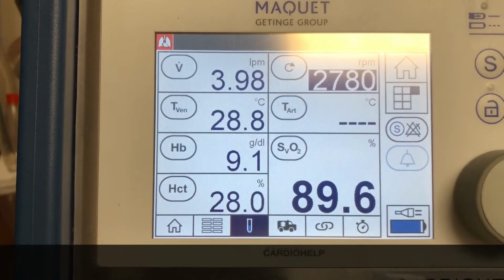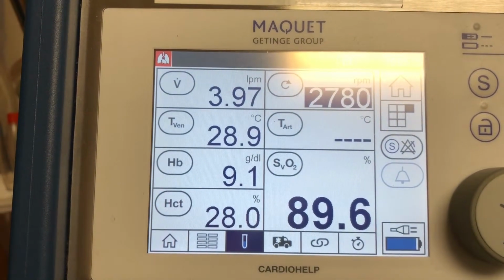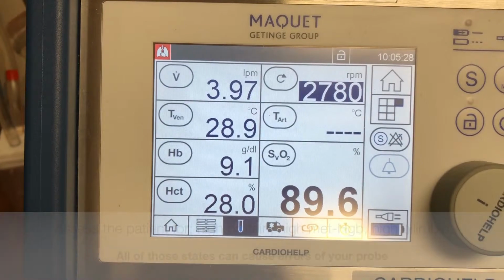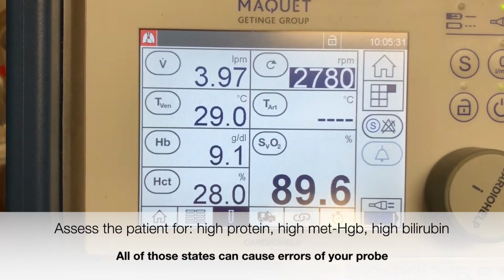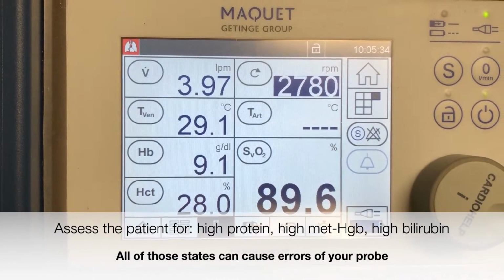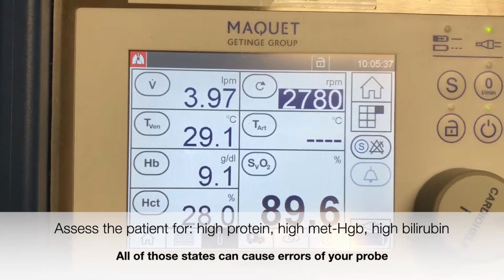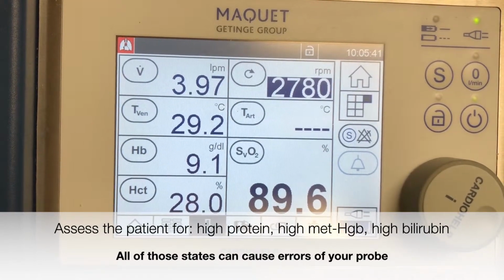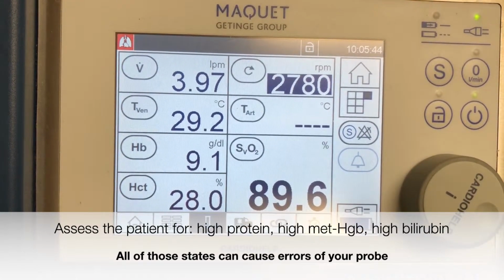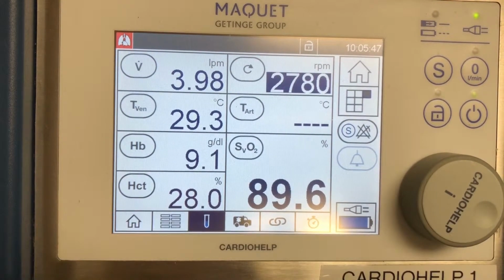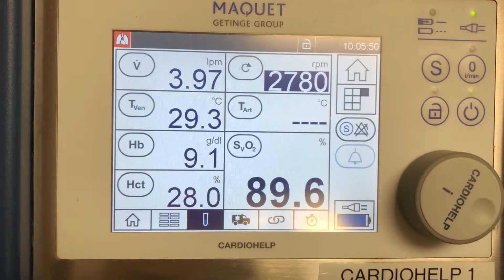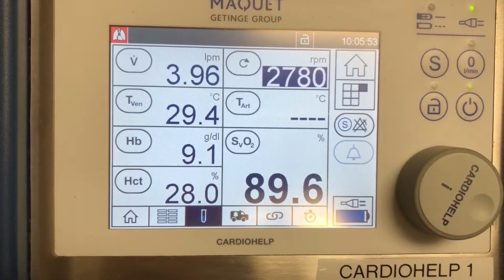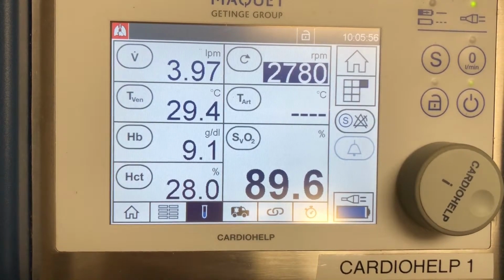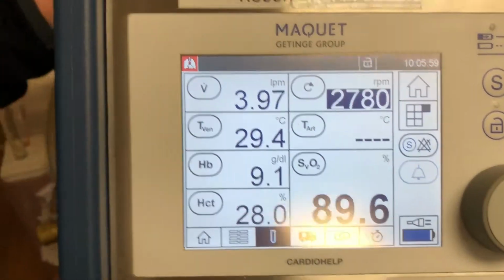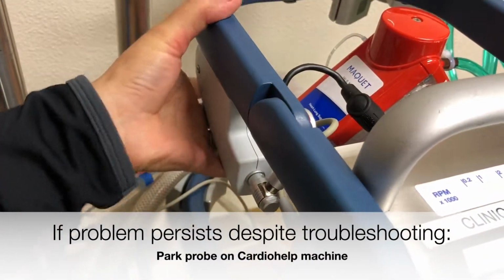If you try all of these, which can happen, and it does not help, there are some issues that can cause this venous probe to have problems reading the values. If the patient has high protein levels, high methemoglobin values, high bilirubin values, all of those can affect readings on these blood gas machines or venous probes. So also consider all of those. If a patient is on propofol, a high volume of propofol, and that causes a lot of protein circulating in the body, then I would consider that as a reason why it's causing it. If that's the case, there's nothing you can do. I would just park this venous probe up here and live without my venous.